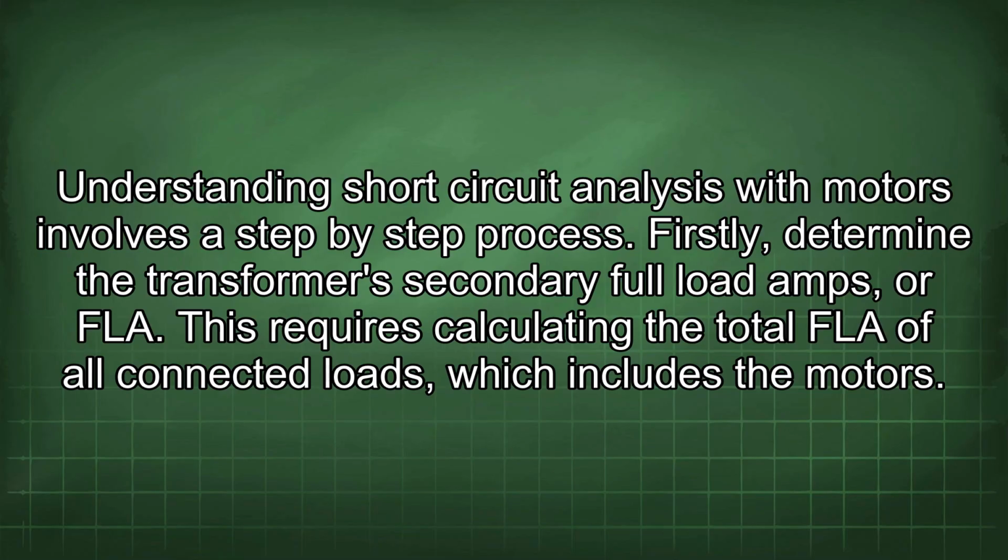Understanding short-circuit analysis with motors involves a step-by-step process. Firstly, determine the transformer's secondary full load amps, or FLA. This requires calculating the total FLA of all connected loads, which includes the motors.